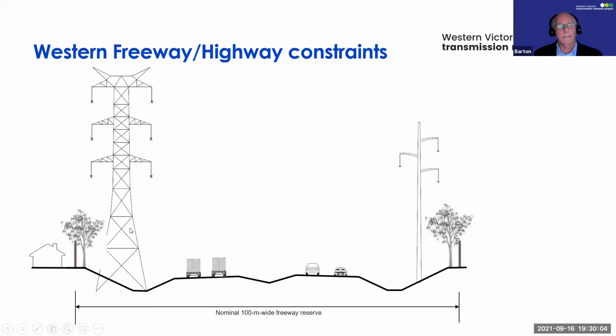Another important consideration is that the easement for a 500 kV transmission line is typically around 80 metres for double circuit, and 40 metres for a 220 kV double circuit. That's designed to ensure appropriate electrical safety and electric and magnetic field clearances for people. When we have houses closer to the infrastructure, as in this case, we need to raise the towers or poles vertically to achieve the separation we can't achieve horizontally.